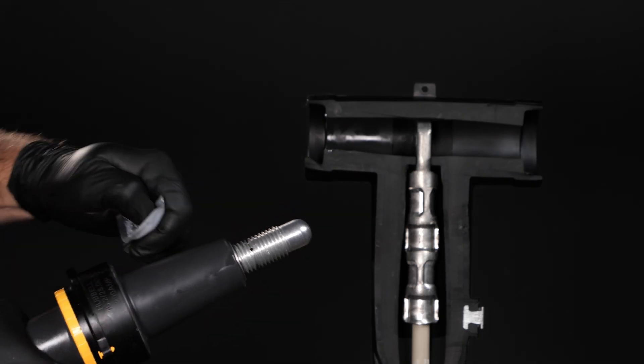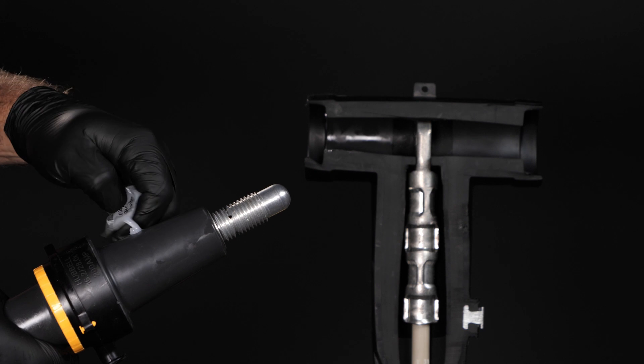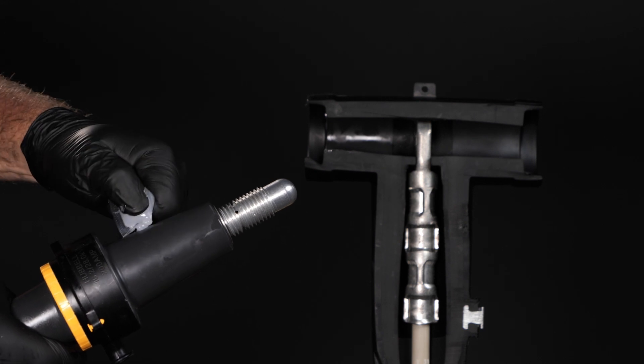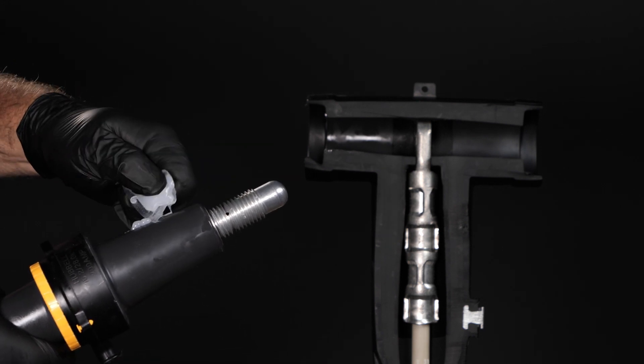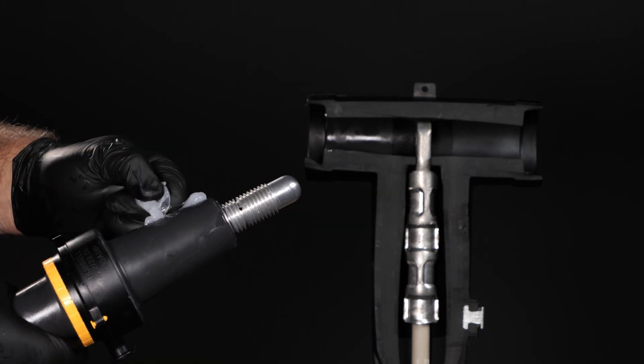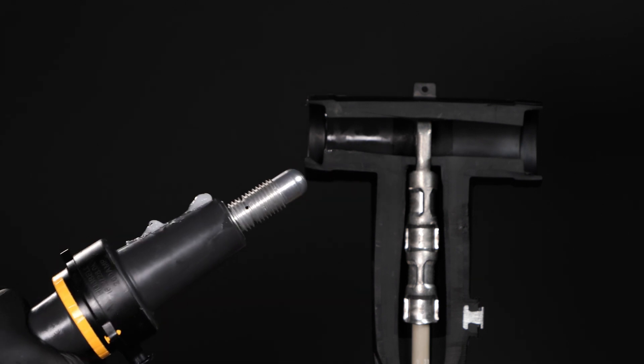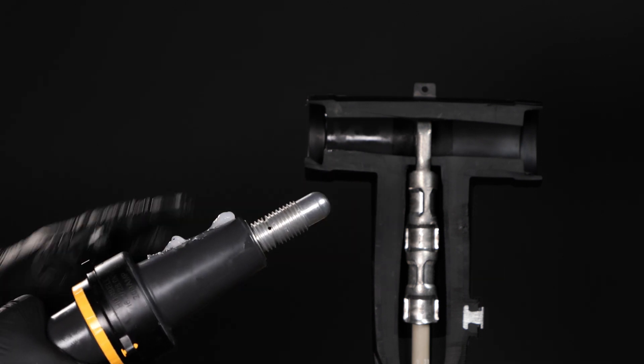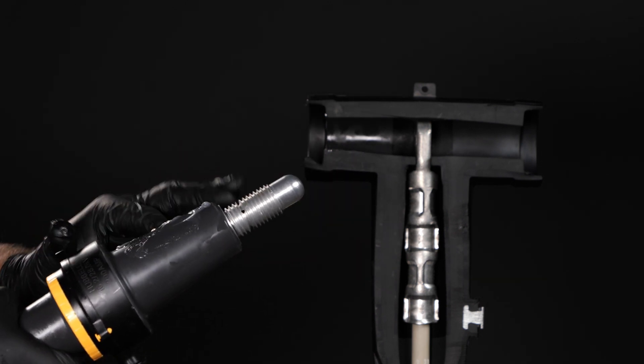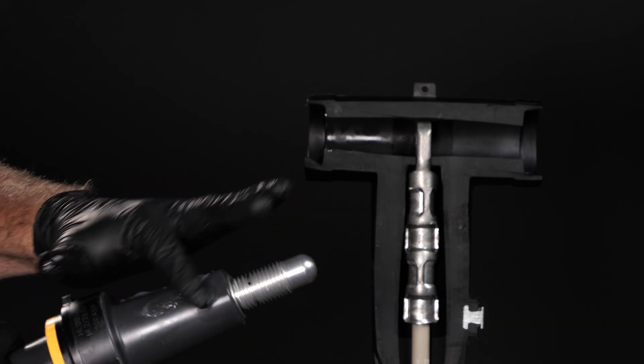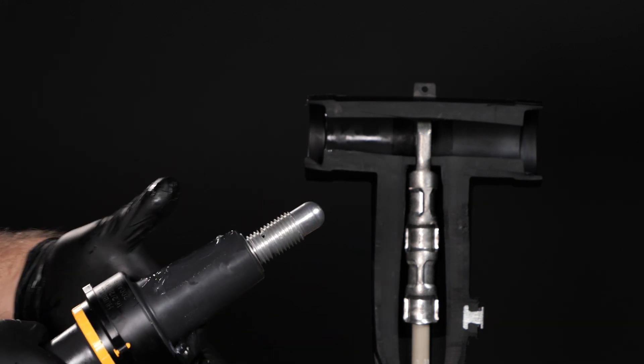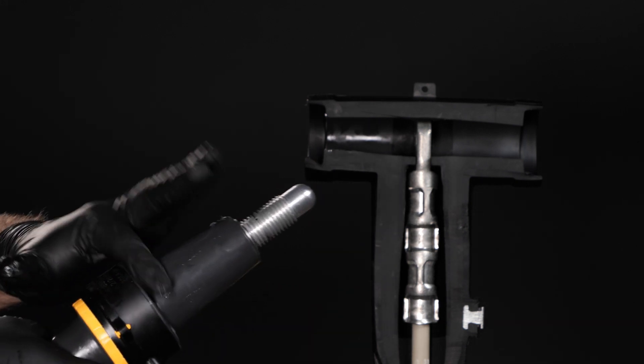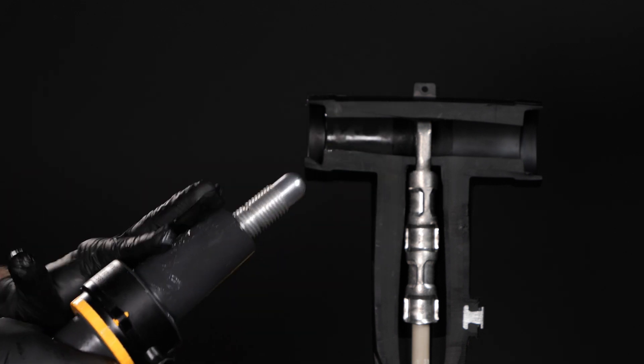Once the cable has been prepped and T-body installed, begin the SureTap installation by cleaning the interfaces of the SureTap and T-body. Next, add a thin uniform layer of silicone grease on the SureTap interface that will go inside the T-body. Silicone grease aids installation and helps fill small air voids that will create partial discharge.